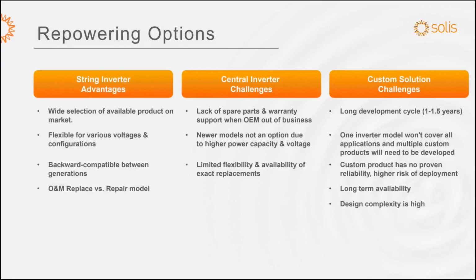Next, we will compare repowering options. There are several options available for repowering: using string inverters, possibly using some central inverters, or designing some kind of custom product that could accommodate the application. First, we'll review the advantages of string inverters. Wide selection: as we show, we have 5 products that could do the job, and we can fine tune the product to the specific repower project. Flexibility for various voltages and configurations: we can accommodate low voltage on the DC side, and low voltage and high voltage on the AC side. So it's very flexible from that perspective.